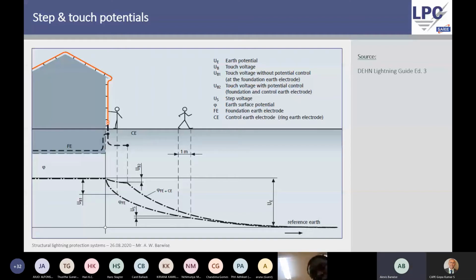We had the words given to us earlier that a down conductor system should safely and controllably, right, bring the currents down to earth. Now, controllably, we have the little guide that said to us, keep it as short as possible. If you have a building that has, for example, here comes a piece out and then the atrium goes inside and it makes the weirdest, most wonderful architectural puzzle piece. That's great for an architect, but lightning's not going to follow this architectural outside of the building. Try and keep these down conductors as straight as possible from the roof all the way down to earth.